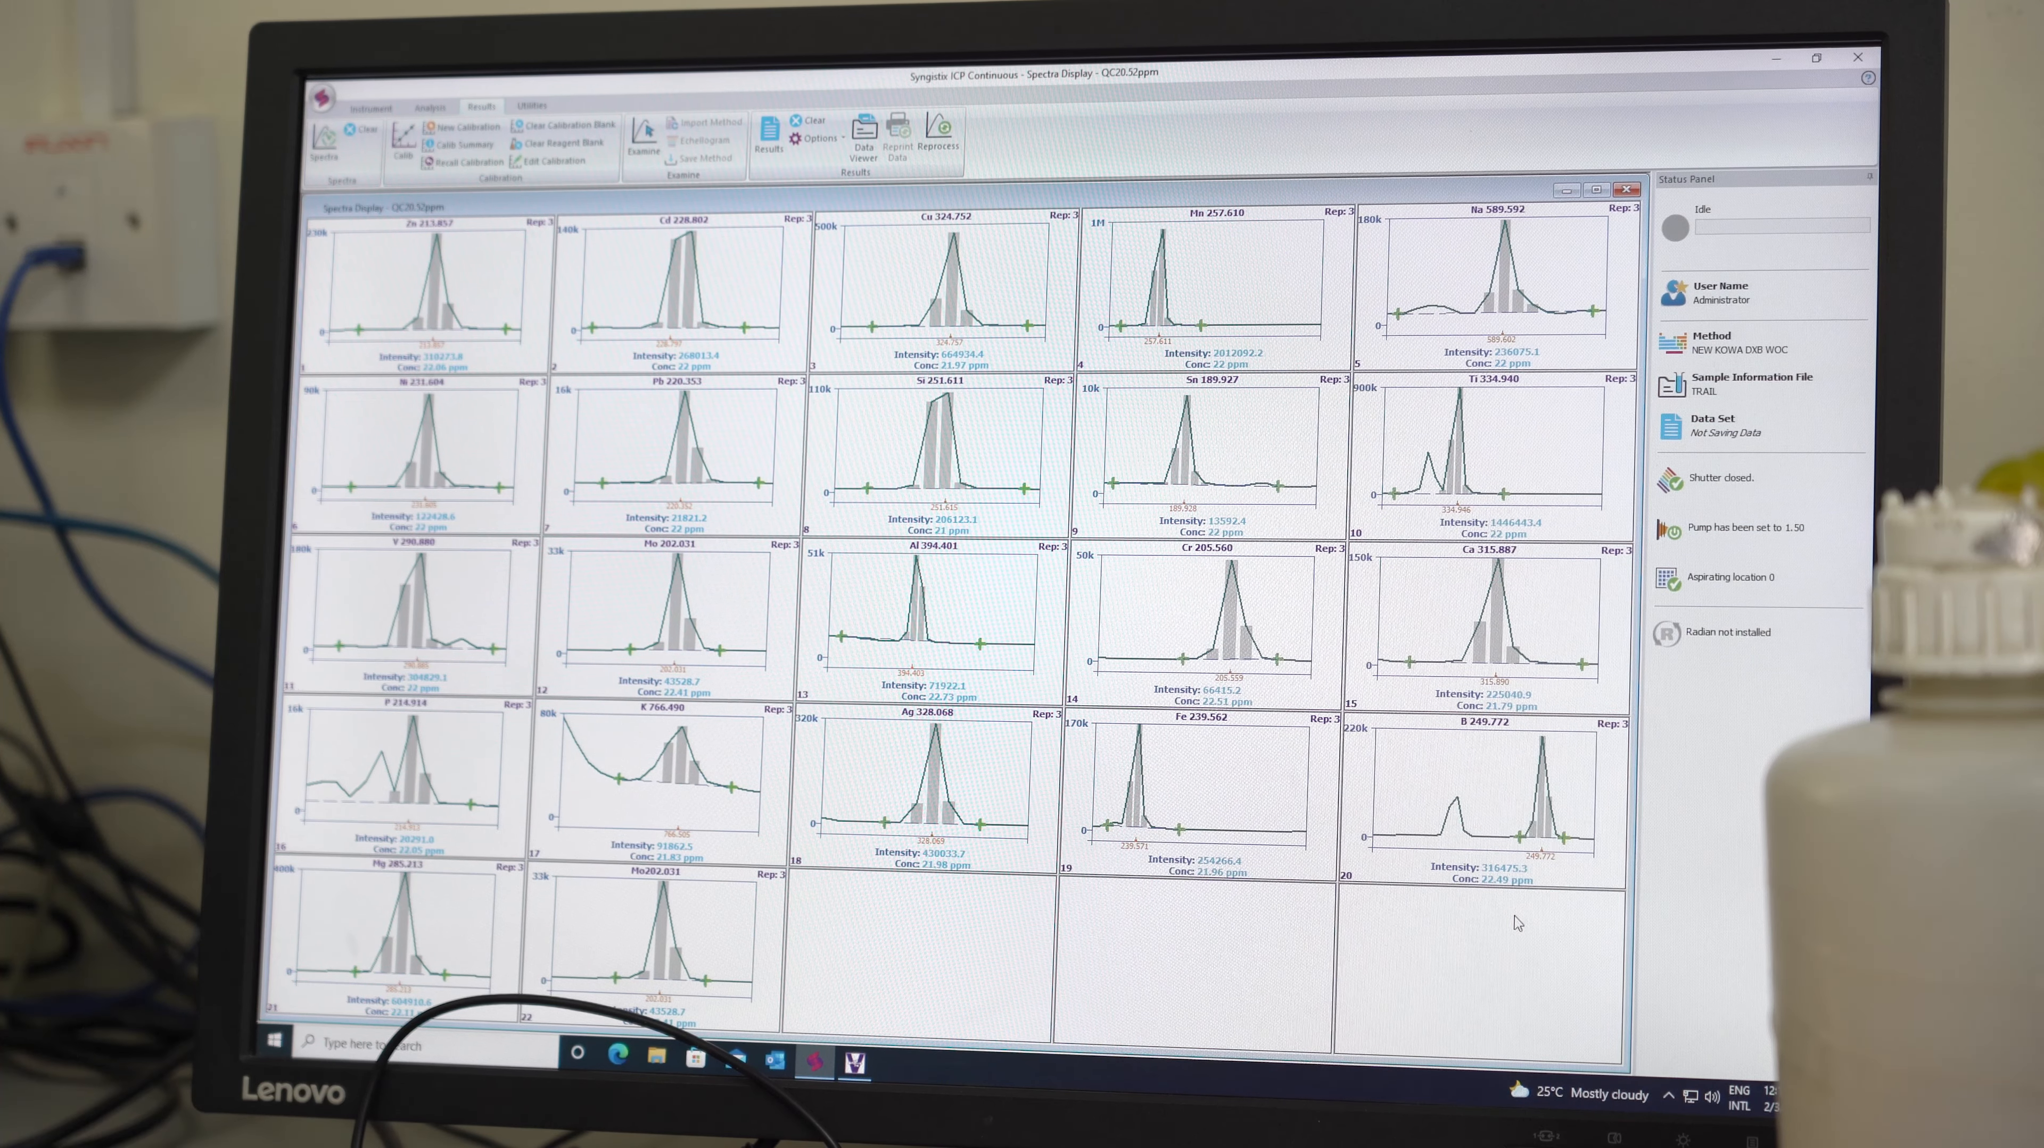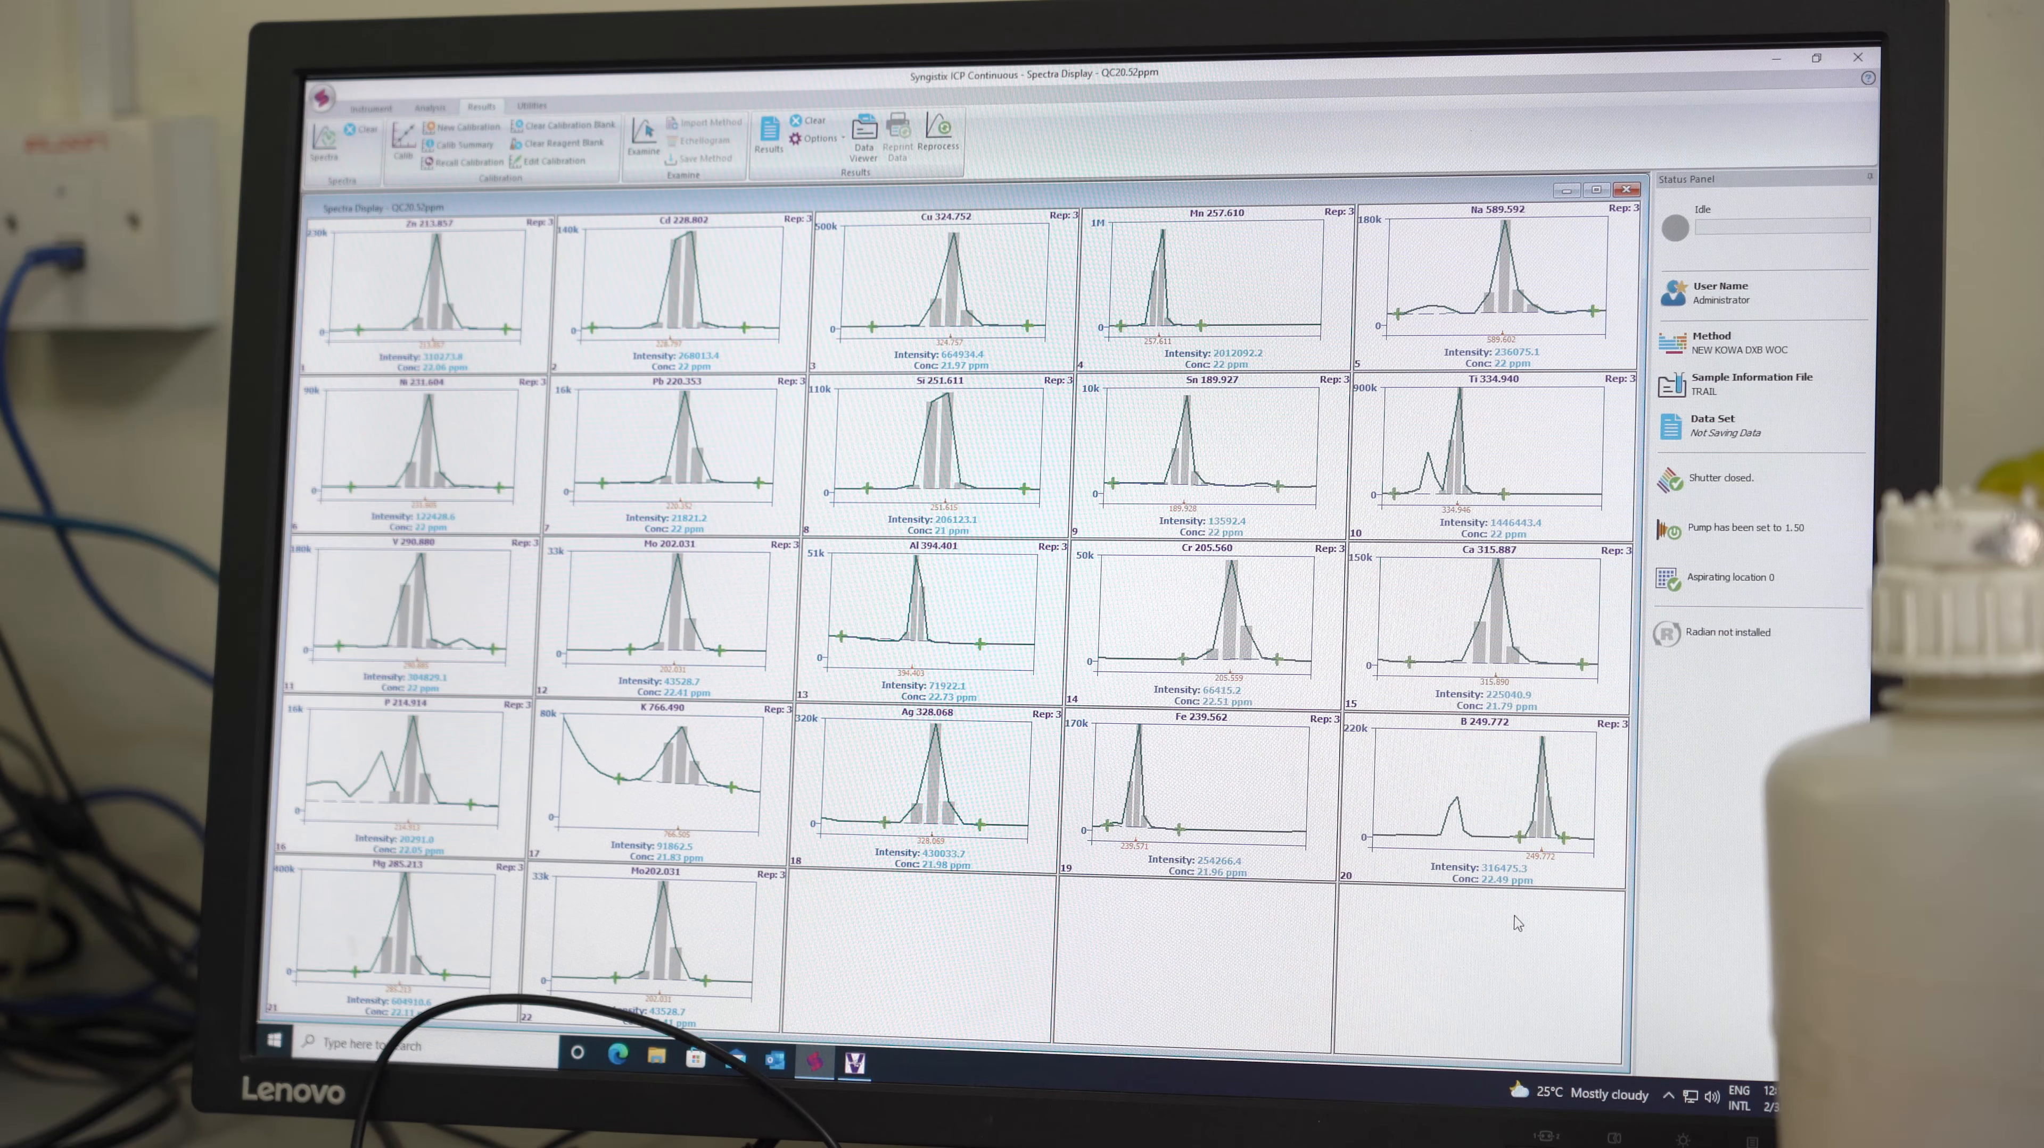The data collected is compared to historical data and is used to establish trends in wear and contamination. The data is also used to monitor whether wear and contamination elements are increasing or decreasing, or if there is a sudden spike in concentration of an element.